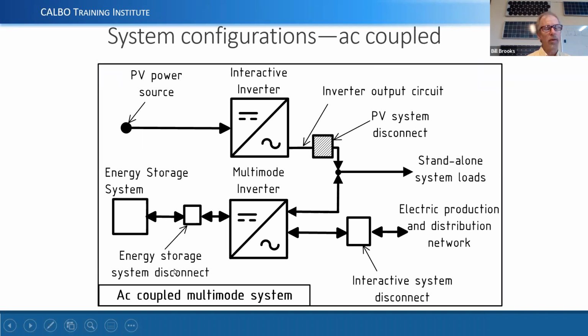And with AC coupled systems, we might be feeding it through a multi-mode inverter and connecting it to the backup side of the multi-mode inverter. So the existing PV system's circuit breaker would be taken out of the main panel, or wherever it was installed, and then be installed in a panel that includes the backup system loads. This is kind of a hybrid in that the energy storage system is being supplied on the DC side.